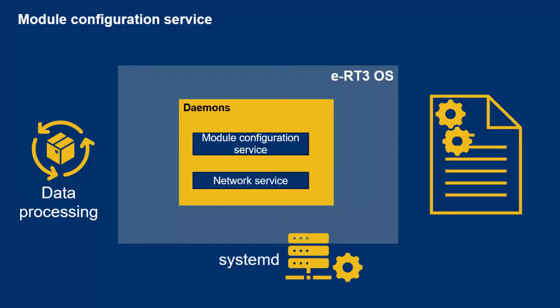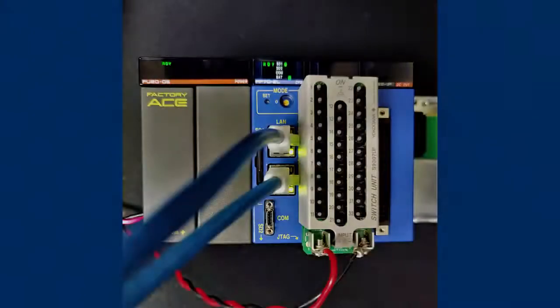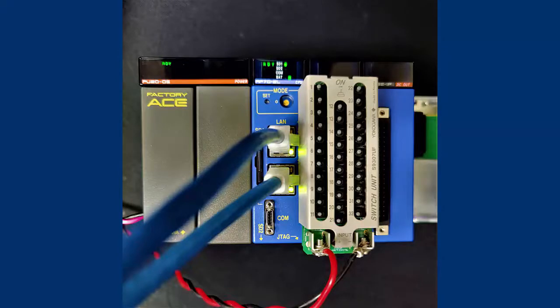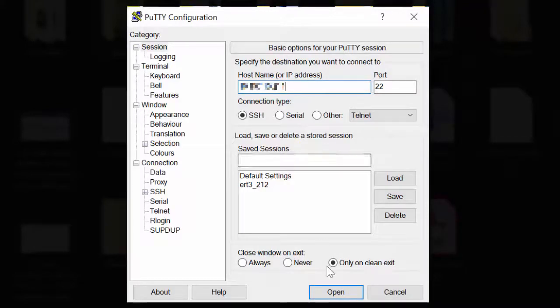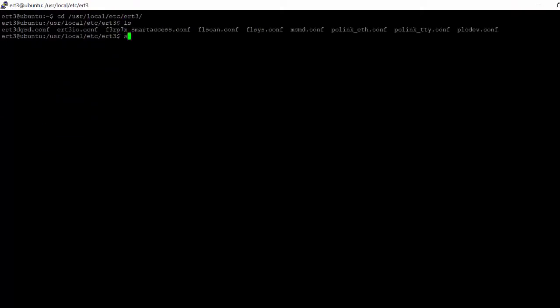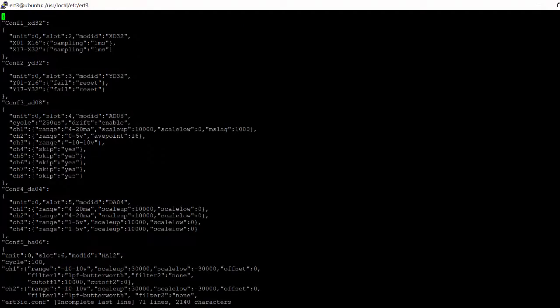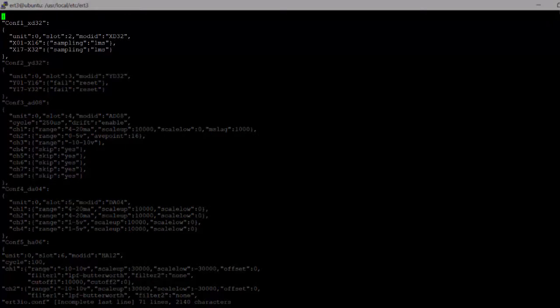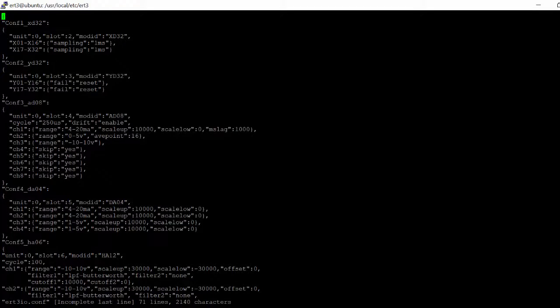In our setup we have connected a power supply, the ERT3 Plus device, a digital input module, and a digital output module, so we must modify the IO configuration settings file accordingly. Login to ERT3 Plus using PuTTY, navigate to the directory containing the IO configuration settings file using the cd command, and open the configuration file in sudo mode to edit the module settings. The configuration of each IO module is specified in standard JSON format. The digital input module settings are in the first object and the digital output module settings are in the second object. If you have additional modules, you can define their configuration in subsequent objects.